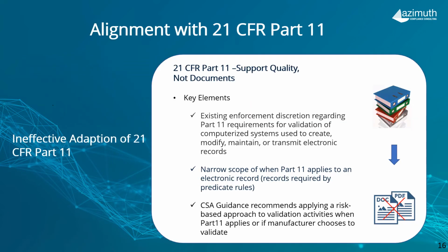Why did I say the ineffective approach to 21 CFR Part 11? The reason goes back to the initial purpose of Part 11. It was the creation of audit trail and electronic signature records as they related to the predicate rule. Where industry went wrong is the rule was applied to everything in an automated system. All testing required a proof of audit record creation, and in some cases that electronic signatures were being captured every time a record was changed.